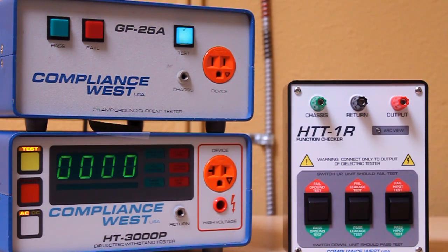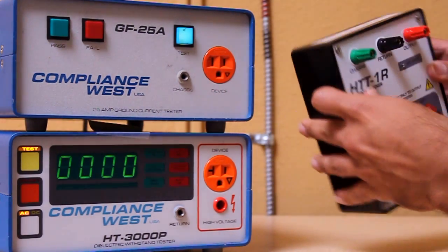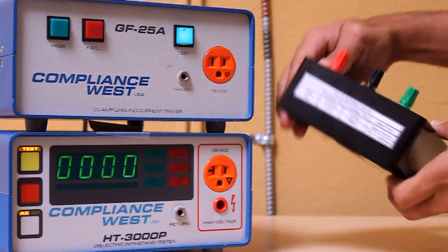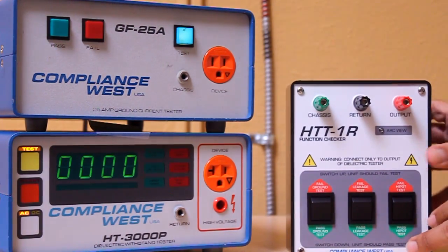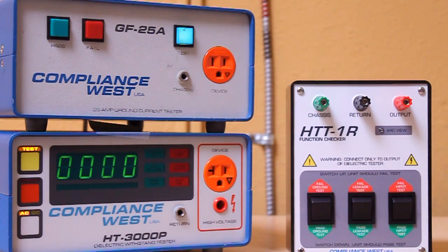and ground bond tester in use are checked by realistic component values which mimic the characteristics of your production items. The values used in each HTT-1R are marked on the enclosure for quick verification. The HTT-1R verifies the result of the 3 failure modes encountered in production, Hipot, and ground circuit testing: open ground, high leakage current, and dielectric breakdown, to verify proper test equipment operation.